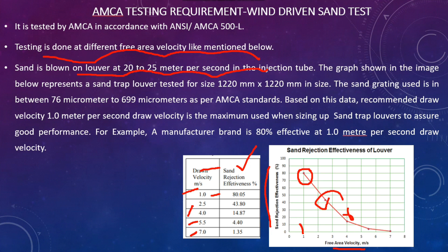Based on this data, the recommended draw velocity is 1 meter per second as the maximum used when sizing. That is because the manufacturer brand shows 80% effectiveness at 1 m/s draw velocity. Different manufacturers have different sand rejection effectiveness. In the project specification, a minimum percentage of sand rejection effectiveness will be clearly mentioned, and based on that the product is selected. At 1 m/s draw velocity, it has the highest performance, which is the reason we always go with 1 m/s selection.